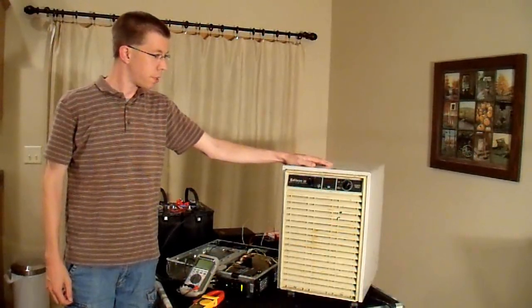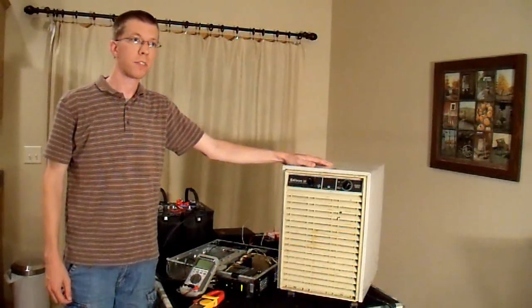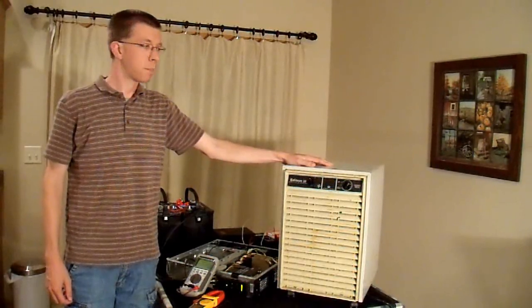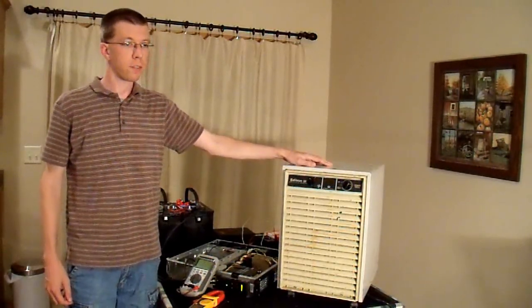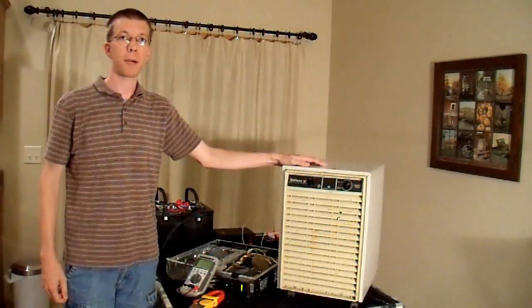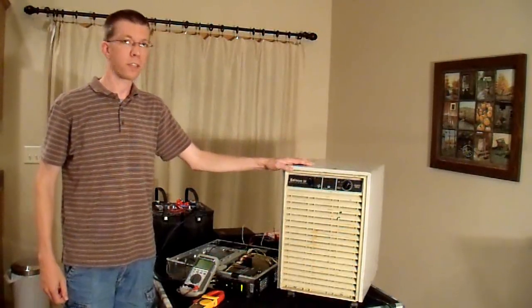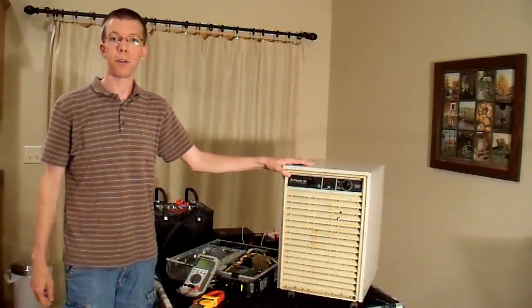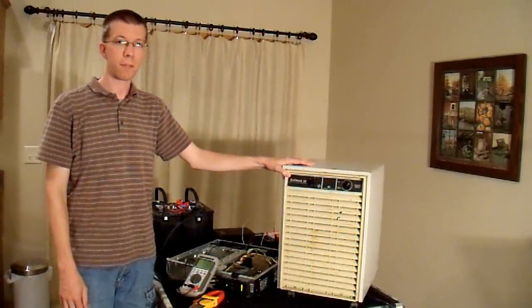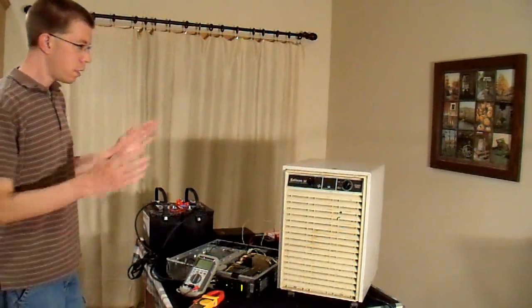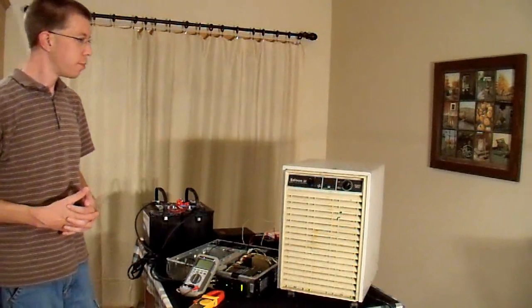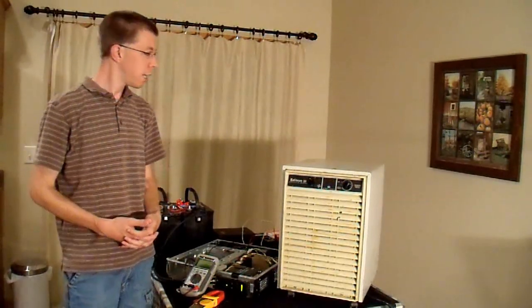This is an older unit with a reciprocating style pump. Some of the new ones have scroll pumps. The reciprocating pump is perfect for this application because when the piston hits its compression stroke, if the motor inside doesn't have enough power to compress the refrigerant, it can't turn over, and I get a locked rotor current measurement out of it. This is probably the most difficult kind of load that a typical household will have. I have an air compressor in the garage that might be a little bit better, but I don't want to haul that inside, so I'm going to use this.